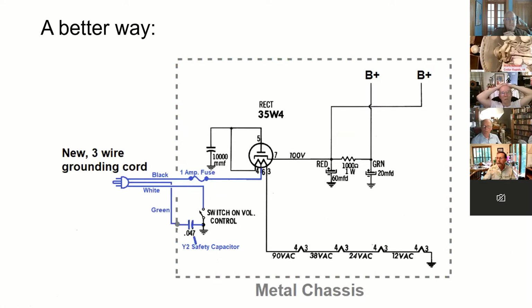The best way to handle this is actually to install, if you can, a 3-wire grounding cord and tie the chassis directly to that green wire that goes back to the neutral bus, in case there is a dead short to the chassis, and that would blow, in the worst case scenario, your circuit breaker at the panel.